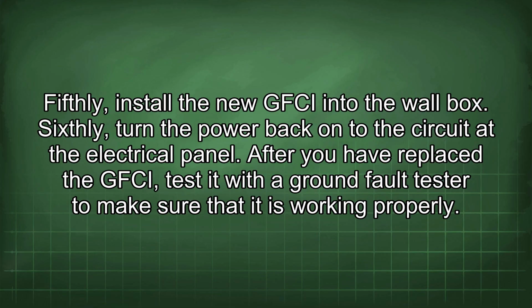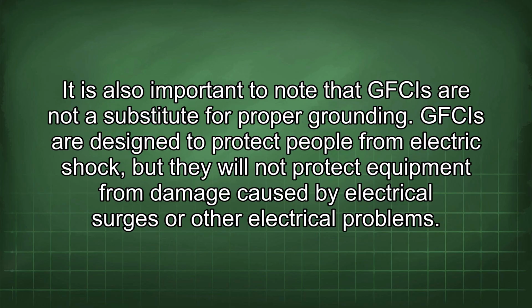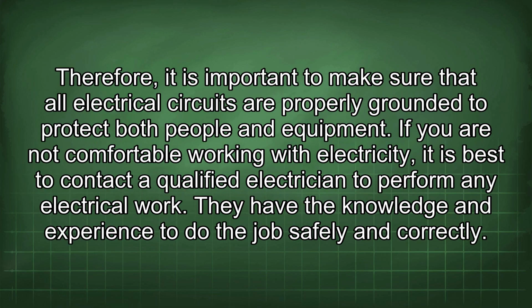After you have replaced the GFCI, test it with a ground fault tester to make sure that it is working properly. It is also important to note that GFCIs are not a substitute for proper grounding. GFCIs are designed to protect people from electric shock, but they will not protect equipment from damage caused by electrical surges or other electrical problems. Therefore, it is important to make sure that all electrical circuits are properly grounded to protect both people and equipment.